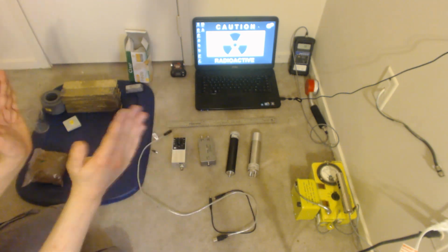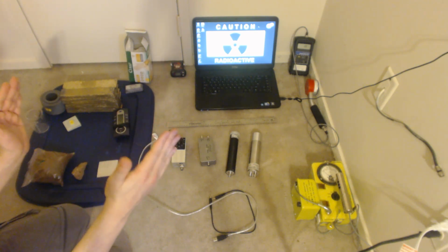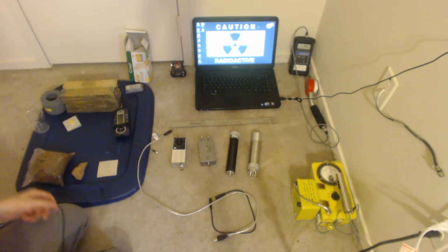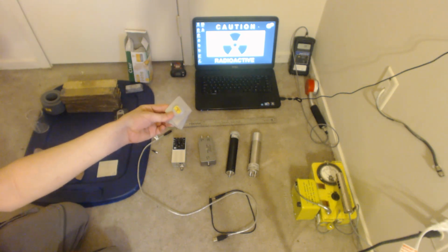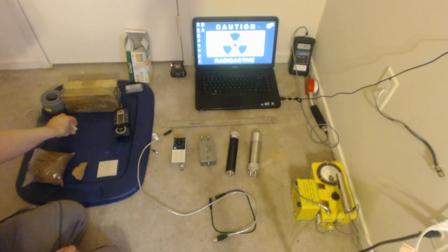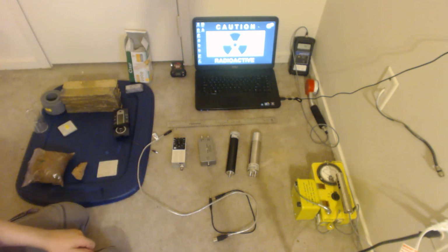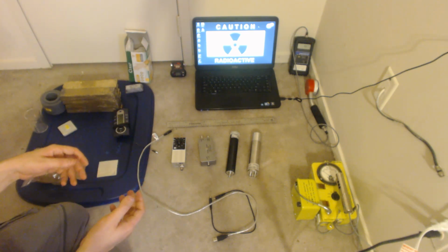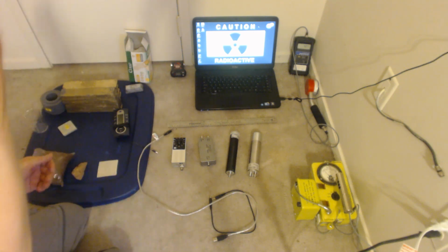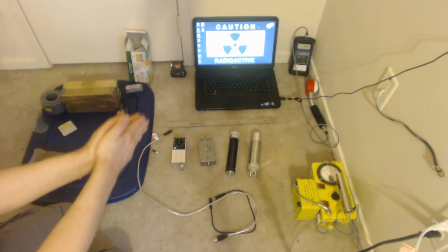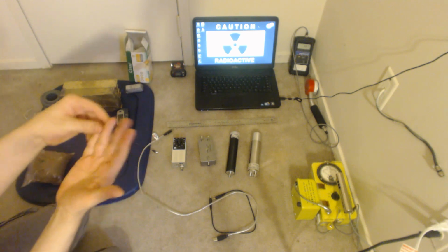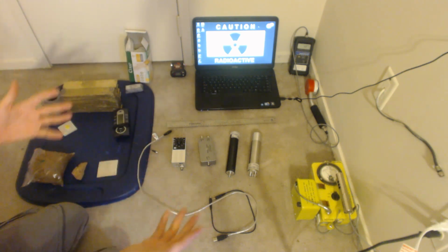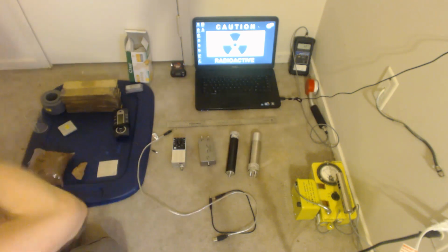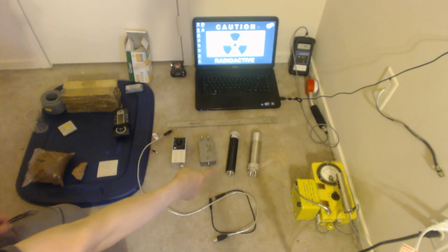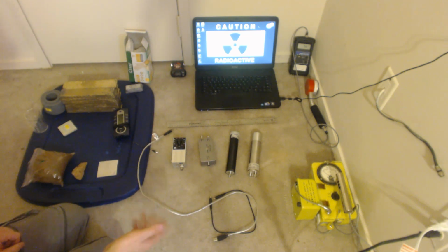For most things, like uranium is going to be down there below 700 kilo electron volts. And cesium-137 is going to be right at 662 kilo electron volts. You know what I mean? Potassium is going to be at 1,461 kilo electron volts. So they're going to fall at different levels, and those different positions that they fall in, those energies, are the fingerprints that you're going to use to detect and identify them anyway. But you need a probe that's wide enough to see all of it, because if you can only see a little narrow part like this guy, then that makes this a really specialized tool that's only good for certain things.